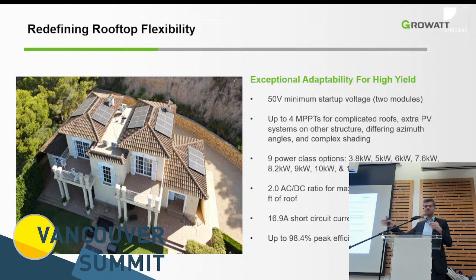10 kilowatts to the grid, plus conversion efficiency, of course, so probably you need 10.25 or something from the DC, and all the excess power that is still available if the battery is not yet full can be charged up to 10 kilowatts roughly into the battery. So you're having a very, very high DC to AC ratio possibility.